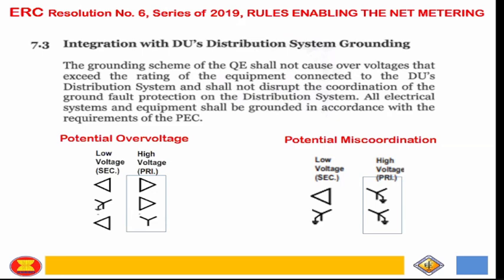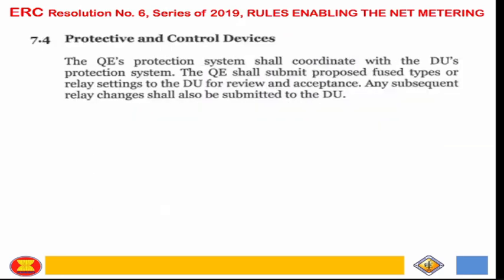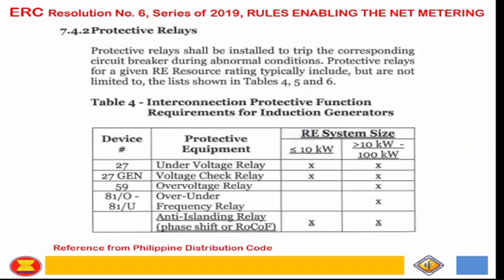Although there's a potential over voltage, but we need to have appropriate protection, no? Although we cannot avoid yung potential over voltage, but as much as possible ma-isolate natin kaagad during islanding condition. So hindi naman may limits naman, may tolerance naman. So protective control device, no? The QE submit proposal, in fact, any protective and control device shall be coordinated with the DU, no, for approval. Okay? And then ito na yung mga requirements, no? Although it's not stated in the Philippine Distribution Code the specific protection requirement, but andoon naman yung specific the protection for the type of generator.